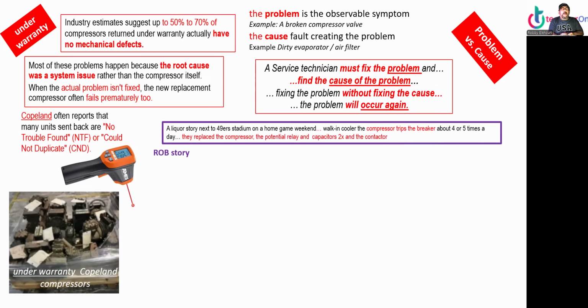Now, a quick story. A liquor store next to the football stadium, and there's a football game going on. Walk-in cooler, the compressor trips the breaker about 4 to 5 times a day. How do you like that? The customer told me they replaced the compressor, potential relay, and capacitors 2 times, and the contactor, and it still trips the breaker. 3 companies looked at it, and nobody could figure it out.